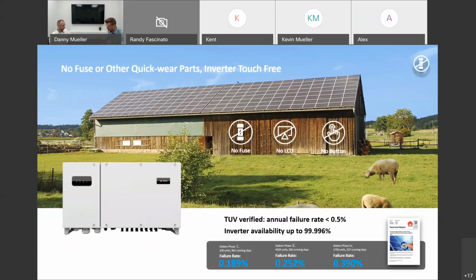Okay, so as a quick overview, reliability is achieved by removing parts that wear and really designing an inverter which is focused on a no-touch concept. So you don't have to do anything, there are no buttons, it's really all programmed. If you wire up, for example, the RS485 to the inverter, you don't even have to set any IDs for each and every inverter. The smart logger together with the inverter auto-assigns IDs to each and every inverter in the field. When you take the inverter out of the box, it already comes pre-configured with IEEE 1547. Once you hook up the AC and DC and you're monitoring, the system would already be code compliant to start right away with you not doing anything. No cell phone app, no display, no button key in, no passcode, no nothing. It literally works out of the box.